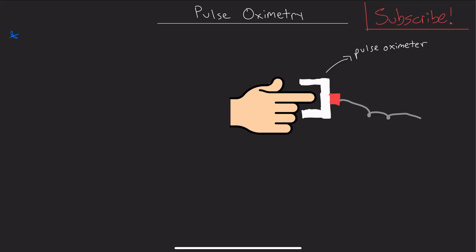The first concept we need to know, and really the major concept of this whole thing, is that pulse oximetry works by measuring light absorption.